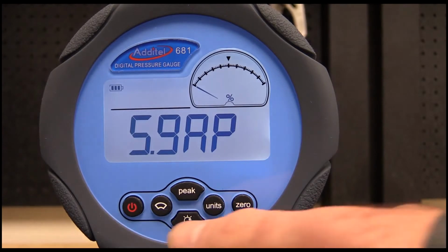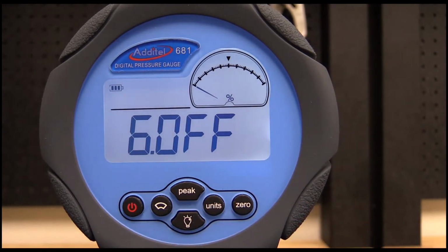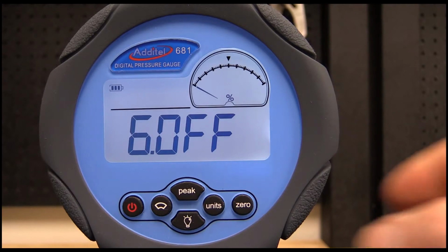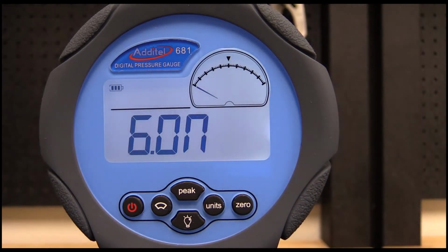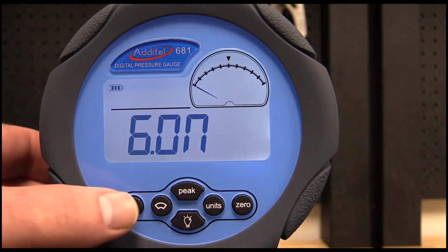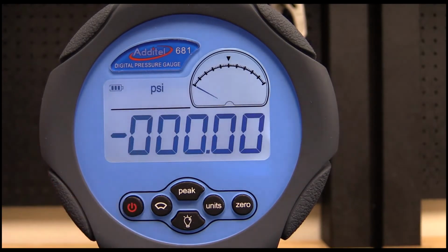The sixth menu is the logging status. Off means that the unit is not logging. To turn on the logging, press the 0 key to change the status to on. You will notice the percentage symbol in the analog window blinking to indicate that a logging session is in progress. To exit out of the menu, press the power button twice or until you are back at the home display. When a log session is in progress, all keys except the peak and backlight keys are accessible.